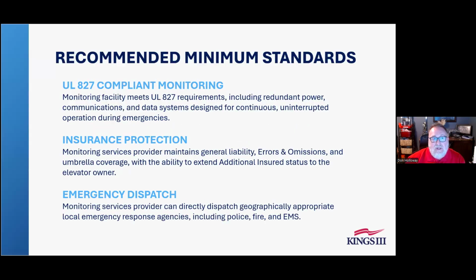Recommended minimum standards: UL listed, UL 827 compliant monitoring. Monitoring facilities must meet UL 827 requirements, including redundant power, communication, and data systems designed for continuous uninterrupted operation during emergencies. Think of this as when you call into a site and power is out in the location.